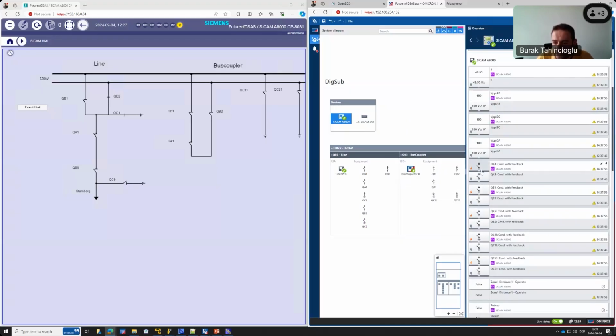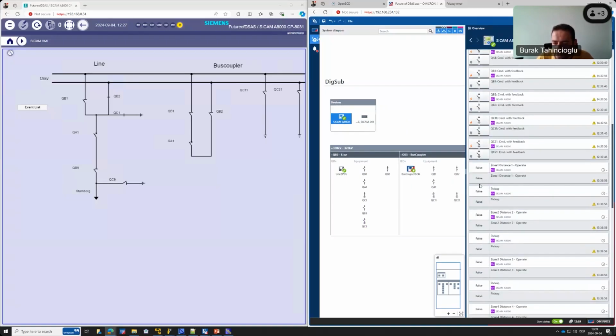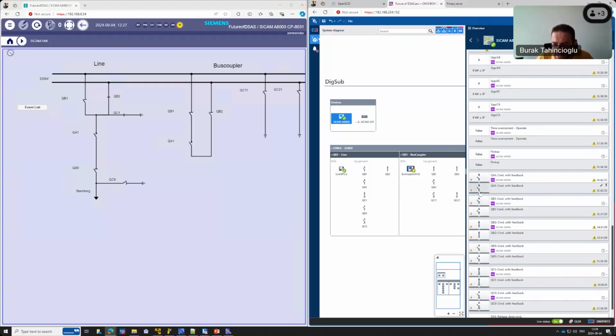I can send the real commands from 6150 to the simulated IED. But what I can also do is with the real IED that I have, the physical IED, I can send the command and see the information changing on the 104 side. And the other way around is also possible - I can send the command from the 104 side and see that the 6150 side is also reacting.